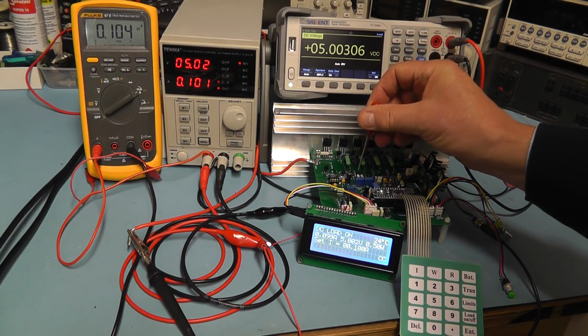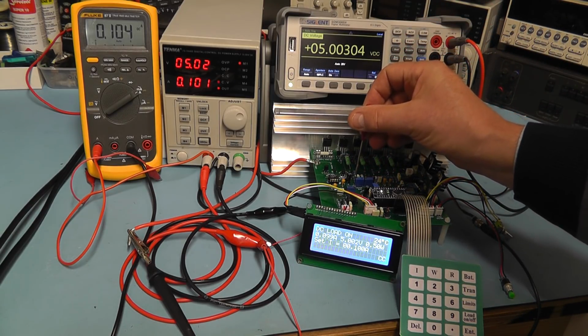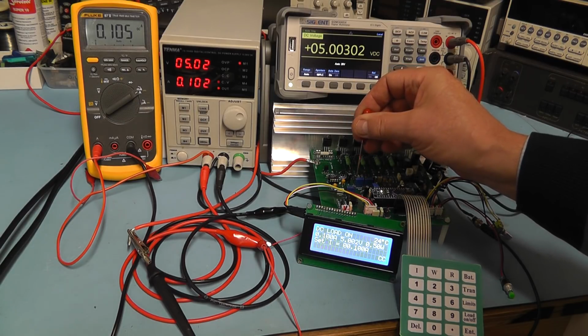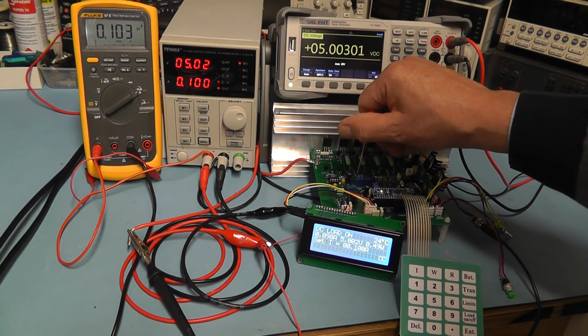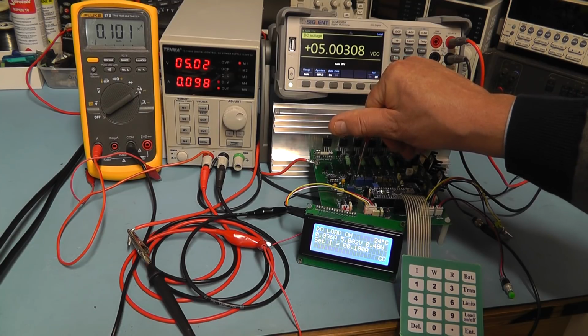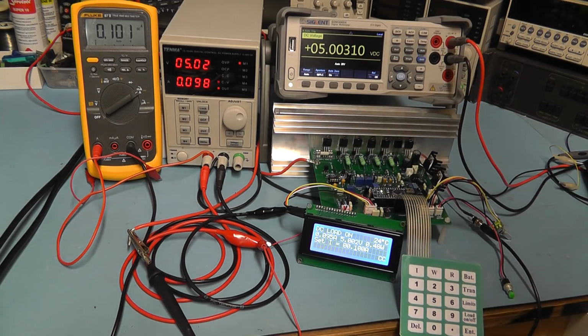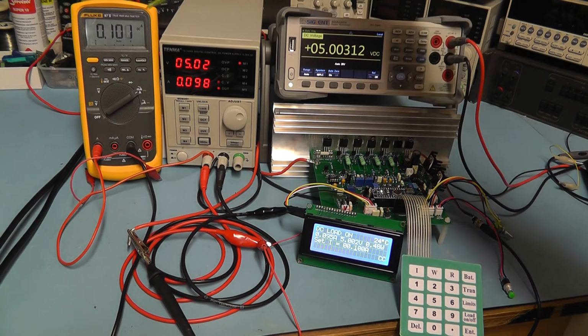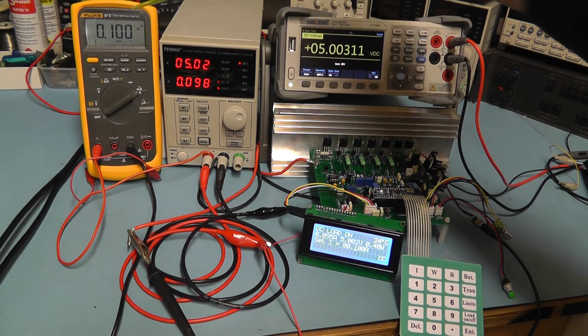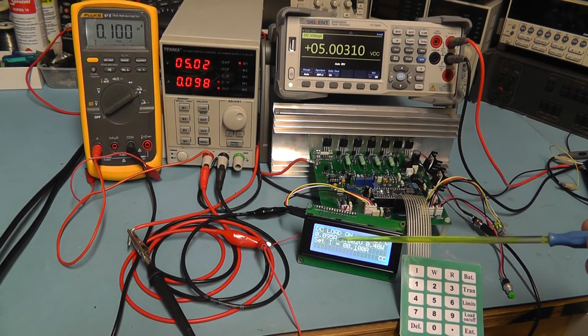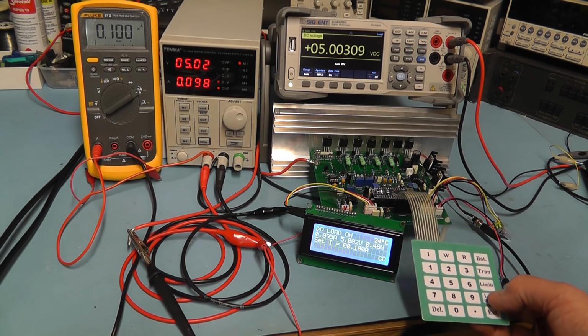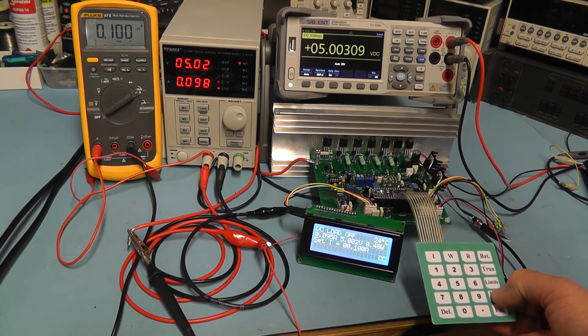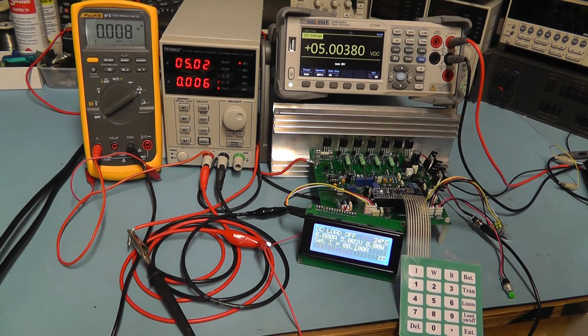and let me adjust RV3 until we can see the 100 milliamps on the meter, just slightly high on the Fluke. About there. So we're drawing 100 milliamps. You can see there on the Fluke. It's actually showing us 0.095 on the DC load, so it's showing us 95 milliamps. So a slight error there. Now we're going to switch the load off again. We're going to now go back and set the load to 3 amps.